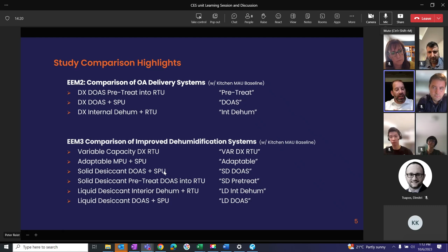So desiccant is an approach to dehumidification where essentially you use almost like an ERV wheel, if you want to picture it that way. And it has a kind of microscopic sieve, and it uses vapor pressure and vapor gradient to draw moisture out of one airstream and deposit into another airstream. And so what they do is they take the moisture out of the outside air before letting it go into the space, and they bring another airstream through the other side that absorbs that moisture and exhausts it to the outdoor air. If you've never come across one of them, you're probably lucky, because they can be a massive headache from a maintenance, a service, a degradation standpoint.